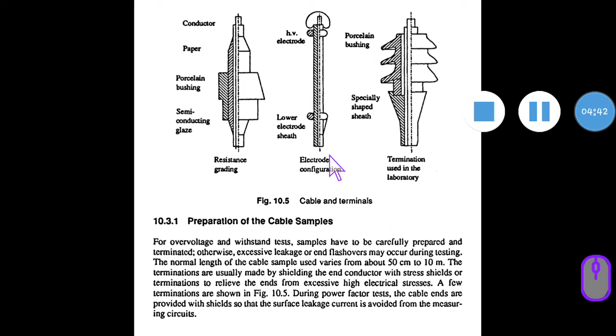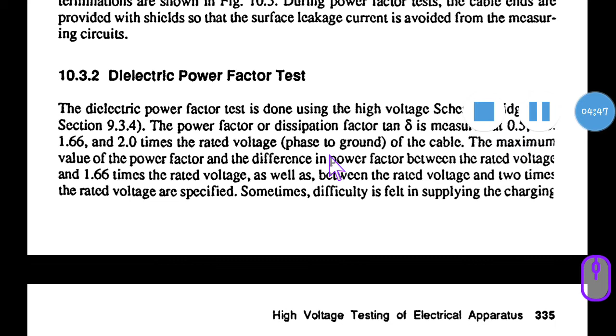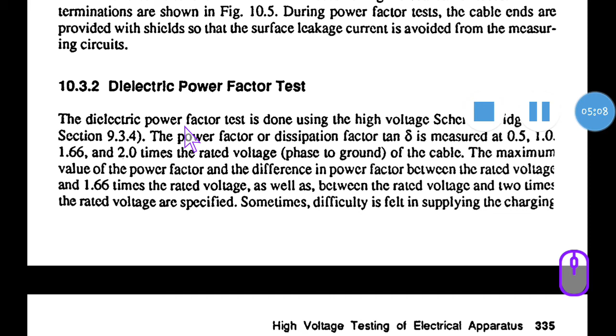Next we will go with another testing of the cables, that is the dielectric power test they are doing. While doing the dielectric power test, here we are considering Schering bridges they are using. Along with this, whatever cable they have erected underground, they will connect with Schering bridges. As you know, starting itself of module 5A, I started with the Schering bridge, so that we maintain the ratio arms and the balance condition has to be maintained. For dielectric power testing, they use Schering bridges and check the power factor and dissipation factor, which has to be measured, during the testing.